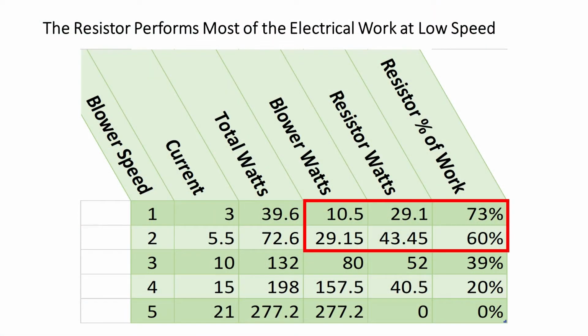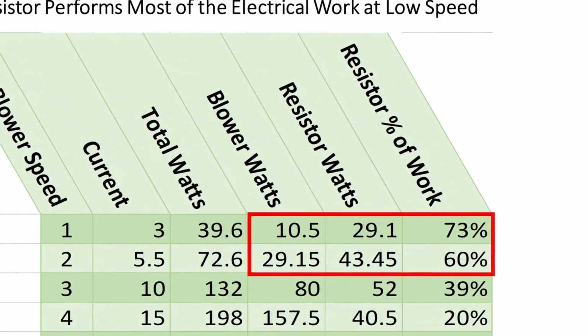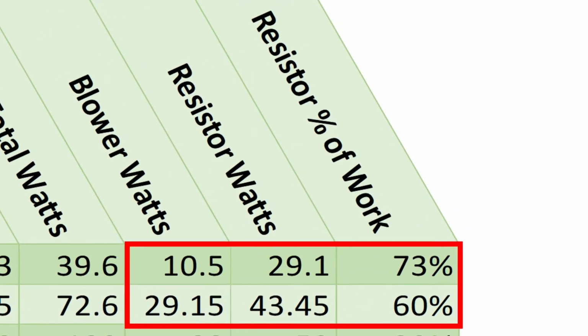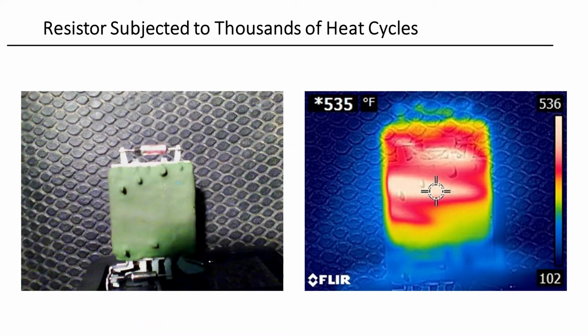This table illustrates the amount of electrical work being done by both the blower motor and the resistor at different speeds in a typical blower circuit. As you can see, the resistor is actually performing most of the electrical work at the slower speeds. This infrared image shows that a working resistor can reach temperatures in excess of 500 degrees Fahrenheit.